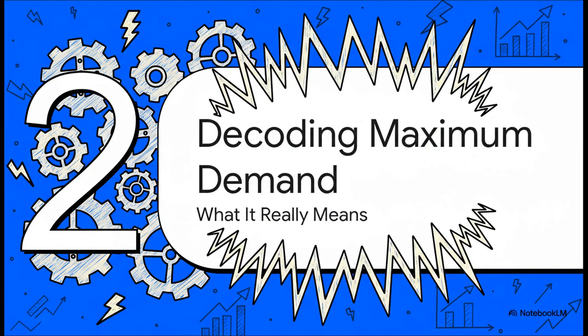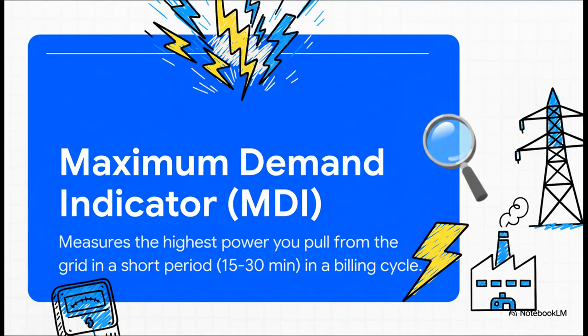So what exactly is MDI? Let's break it down. It stands for Maximum Demand Indicator, and the concept behind it is actually way simpler than that fancy name suggests. So MDI is not about the total amount of electricity you use over a whole month. Instead, it measures your single biggest surge of power, your peak usage. It's that one moment when your facility demands the absolute most from the grid, all at once.